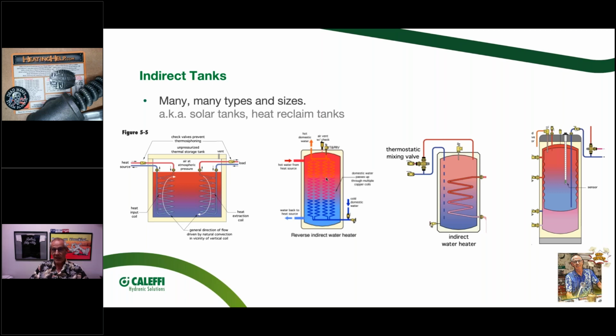If you crank that tank up to 180, 190 degrees, you certainly have a good thermal battery there. That said, you can still run these at lower temperatures if you do the math. I know Pierre up at TurboMax has a good software program his family developed. If you tell them what temperature you want to run the tank at, if you want to maximize the ModCon boiler and keep it in condensing mode, and give him your input temperature and your desired delta T, he can crank this out and size these tanks right down to the exact application.